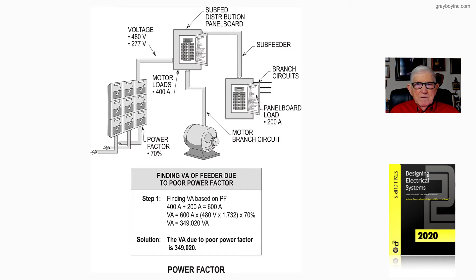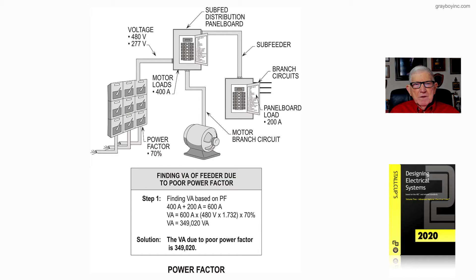This figure 15-2 from Stallcup's Electrical Design Book, Volume 2, shows a condition of poor power factor. When you look at the illustration, we show a 400-amp motor load, voltage is 480-volt, 277, and then we have a load in this panel board of 200 amps, giving us a total of 600 amps. Notice the power factor: 70 percent.